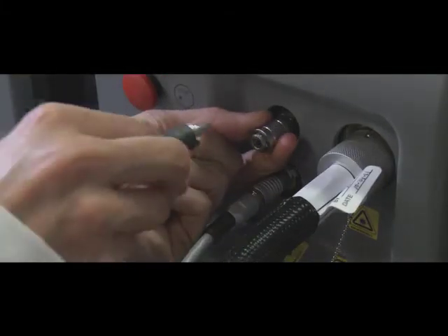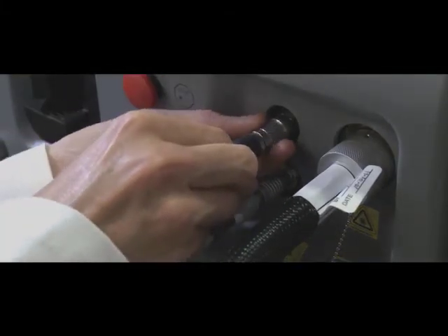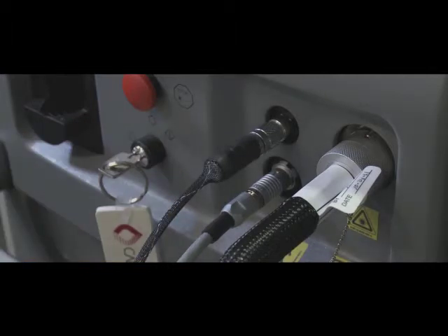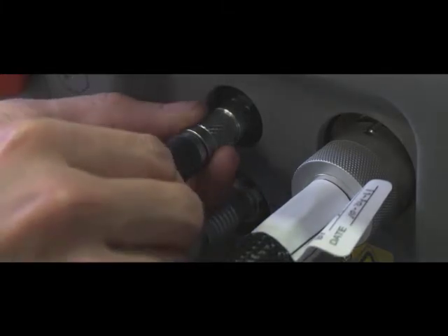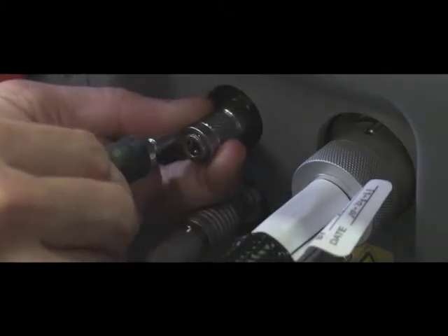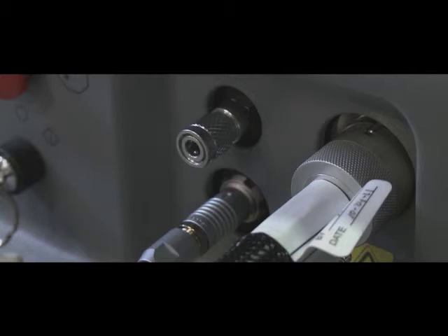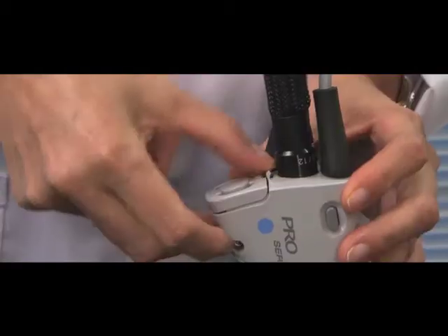When attaching the Cryogen line, you must push in the metal attachment and insert the line. The metal attachment will spring back, securing the line. To release, once again push in the metal attachment. The valve is under pressure and you will hear a rushing sound.